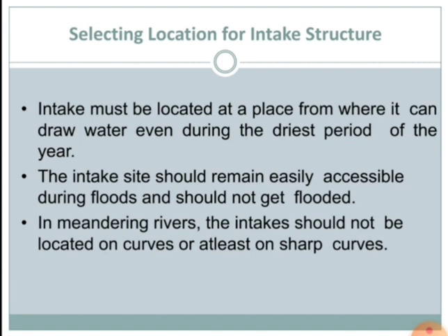Another point to be considered is that it should be located at a place from where it can draw water even during the driest period of the year. That is, this site should be so selected that it may admit water even under the worst conditions of flow in the river, or under lowest possible water level in a lake or a reservoir. So as far as possible, the intake should be located sufficiently inside the shoreline.